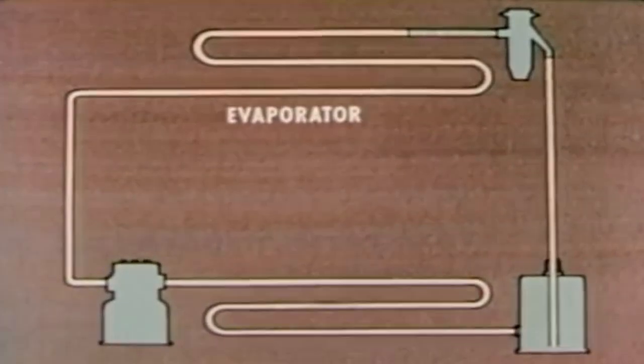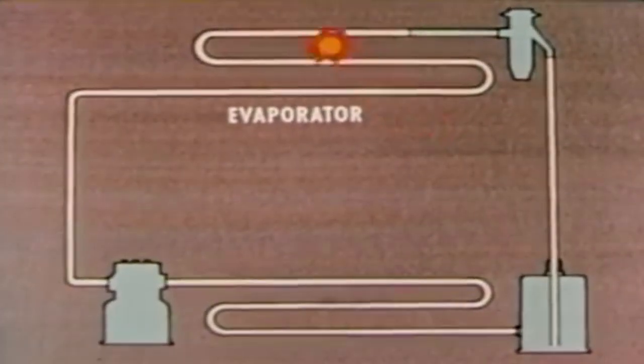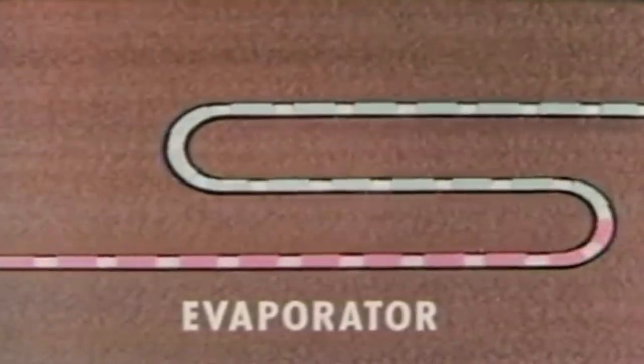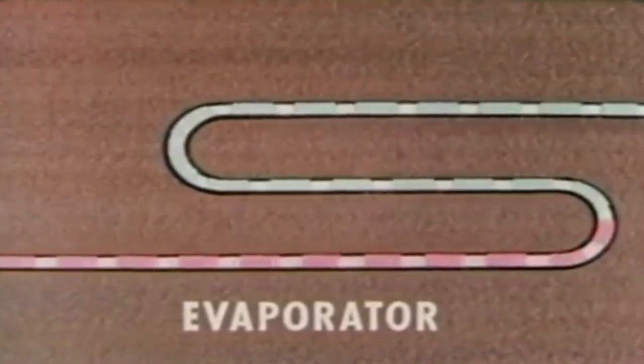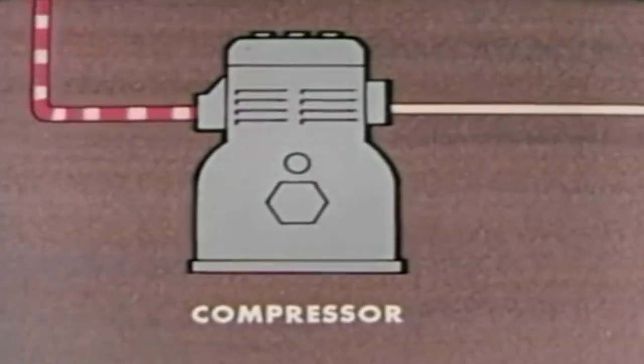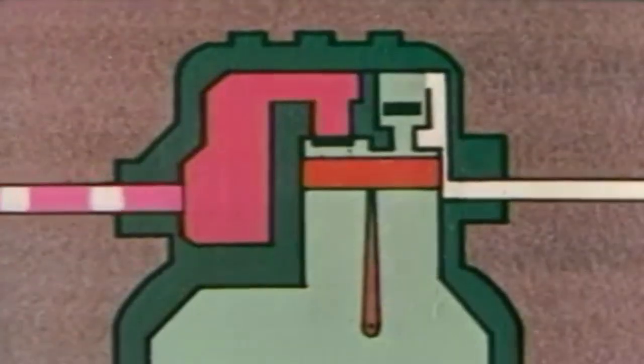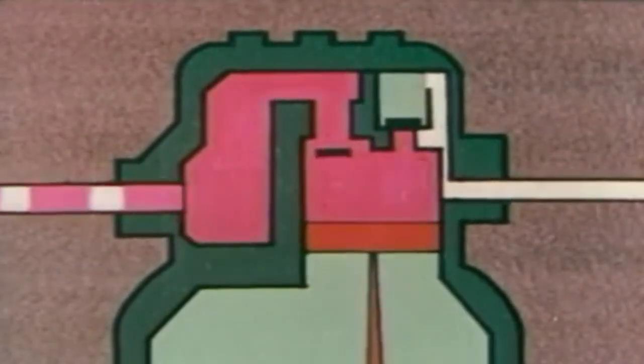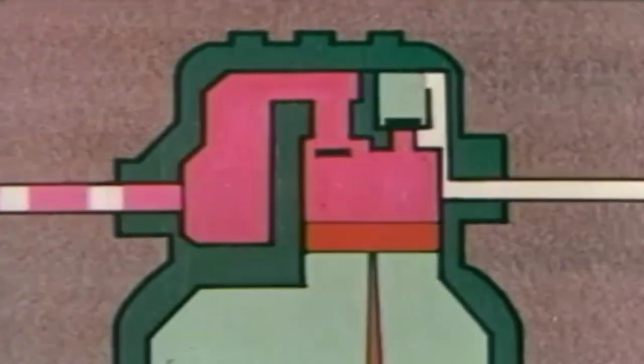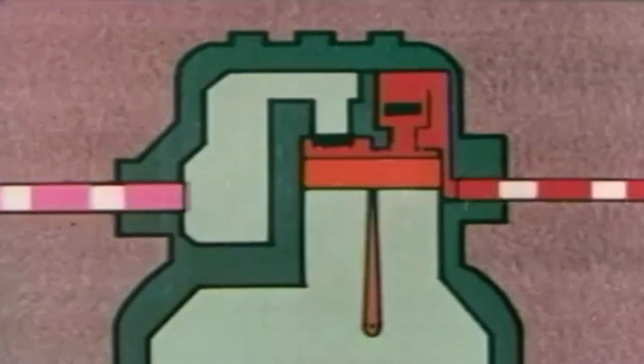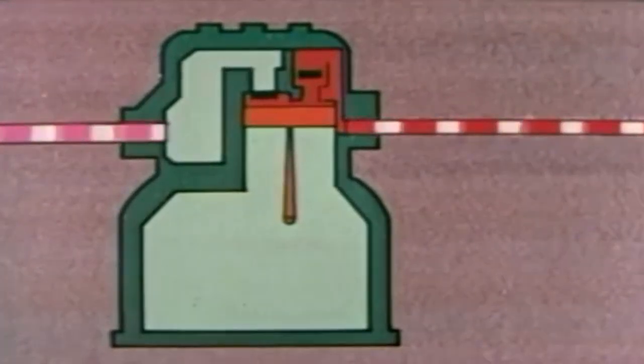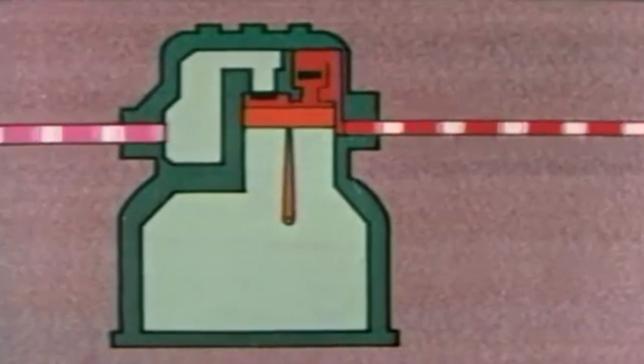If any of the food in the box is warmer than the refrigerant, heat will flow from the food to the evaporator. So in the evaporator, the refrigerant takes in heat and begins to boil. Any substance takes in heat when it changes from a liquid to a gas. The gas is sucked through the connecting line into the compressor. As the piston moves down, the suction valve opens and the gas is sucked into the compressor. As the piston starts up again, the suction valve is forced shut and the discharge valve is pushed open. On this stroke, the gas is compressed.